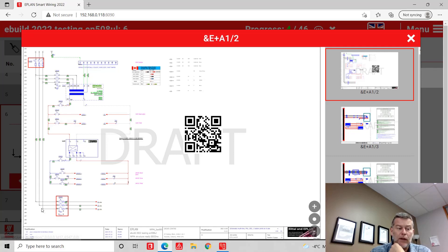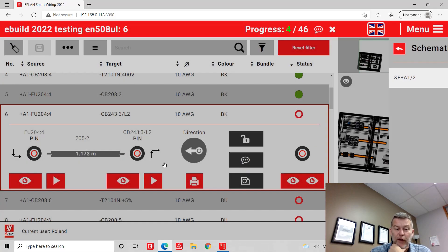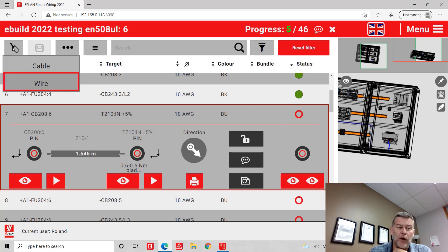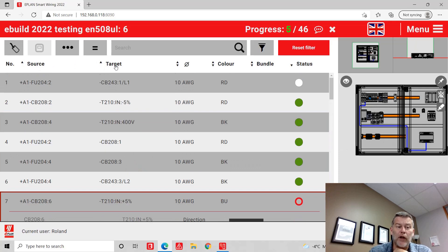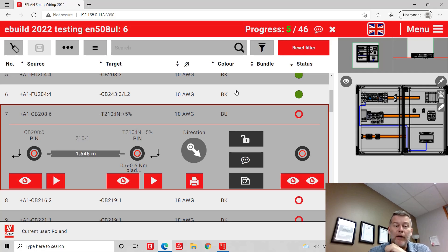I'm playing around in these wires. Here I was connecting pin four to L2 — so it was a second line. As I move forward, I start wiring up the next one and so on. Up here I have the possibility to see cables versus wires, and I can run a sort on the source and the targets. This way I'm not cruising around the whole project too much. I could also place all the colors together, which sorts by color — making installation a little bit easier so I don't have to flip my wires too much. Same thing for the crimping tools. There are different ways to optimize the way you work with this tool.